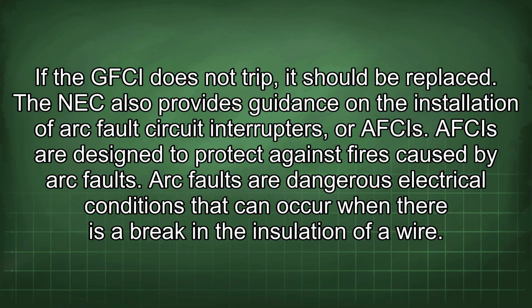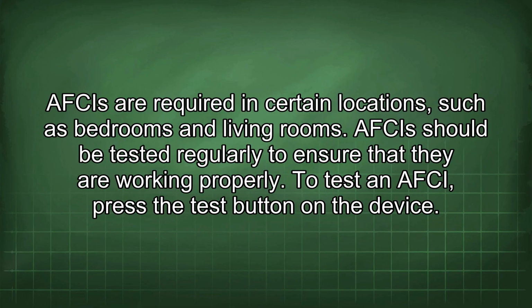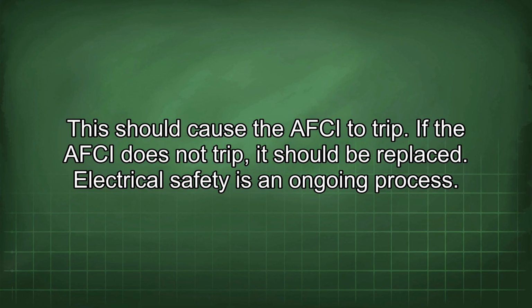The NEC also provides guidance on the installation of arc fault circuit interrupters, or AFCIs. AFCIs are designed to protect against fires caused by arc faults. Arc faults are dangerous electrical conditions that can occur when there is a break in the insulation of a wire. AFCIs are required in certain locations, such as bedrooms and living rooms. AFCIs should be tested regularly to ensure that they are working properly. To test an AFCI, press the test button on the device. This should cause the AFCI to trip. If the AFCI does not trip, it should be replaced.